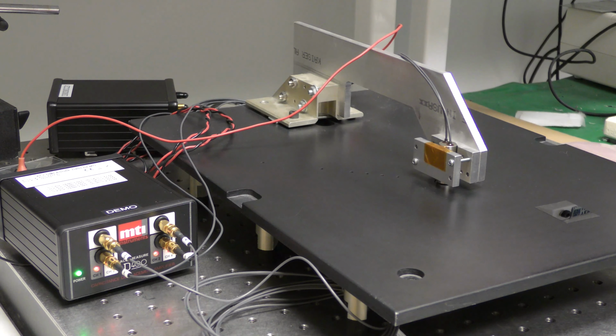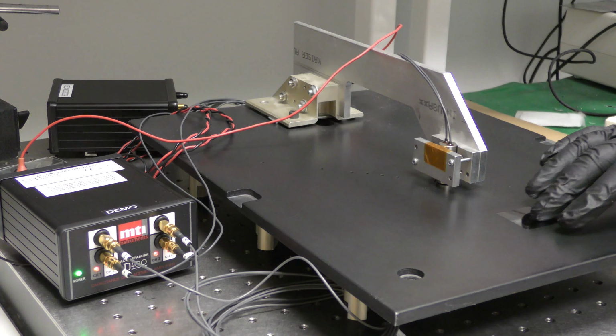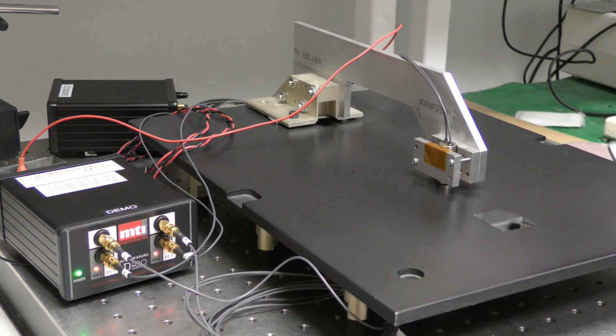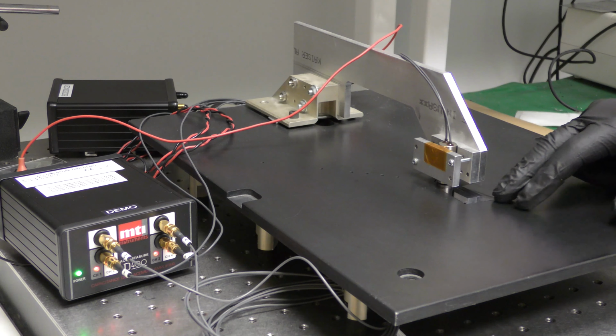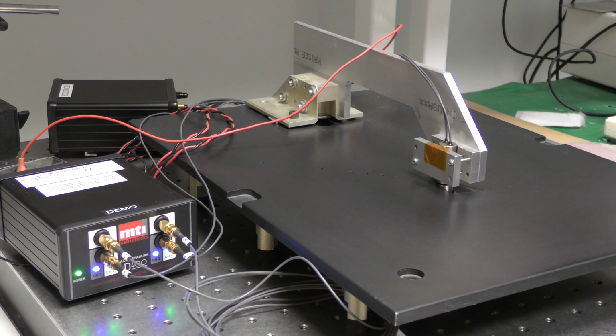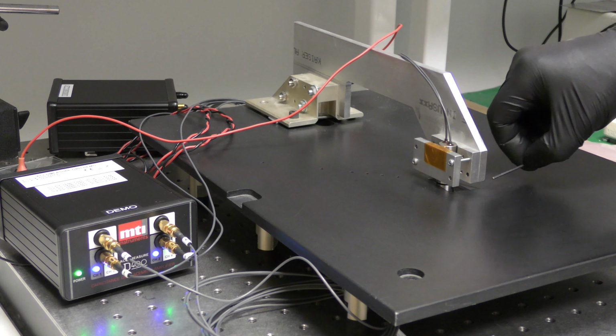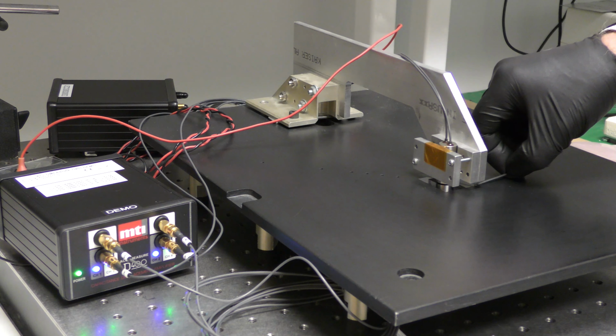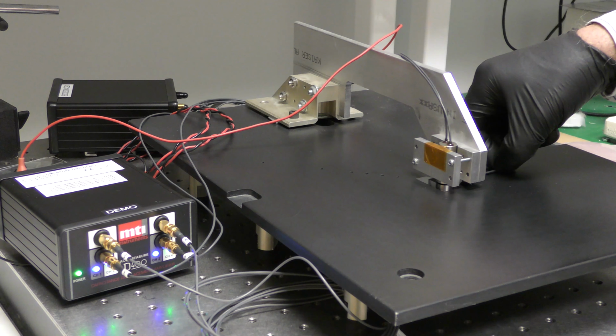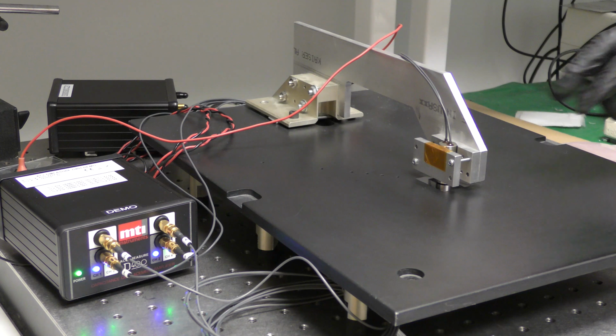Our first step is calibrating the two probes that we have. We have push-pull probes, top and bottom. We have a piece of silicon wafer that has been measured and is 105 microns thick. We're going to slide this in the gap between the two probes. And I'm using this Allen wrench to get it centered in there. All right, so our test sample's centered, and we're going to come over here.